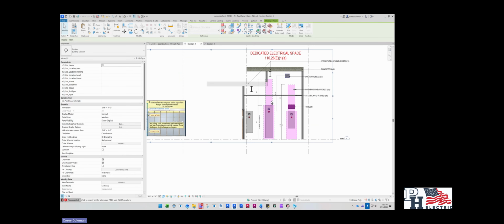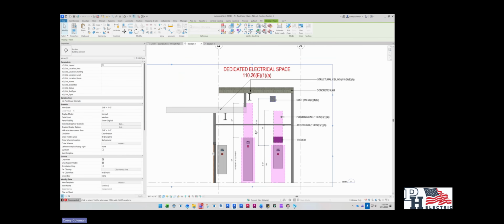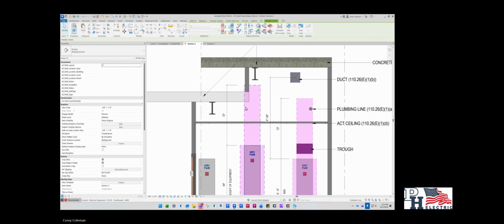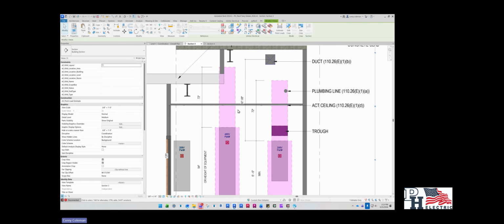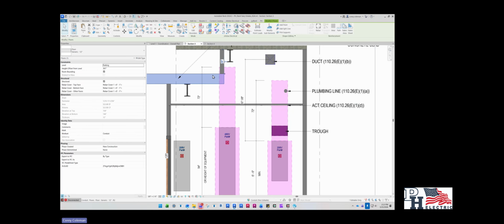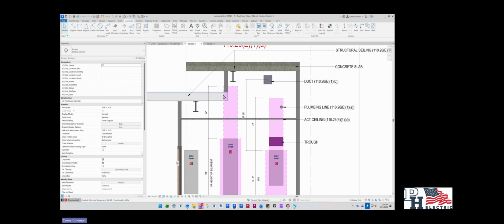And then lastly, when we're dealing with dedicated electrical space, you can have structural ceilings above it, but you cannot have any other foreign elements in that space. So for instance, this ACT ceiling, because of 110.26(E)(1)(d), is allowed to be here as a removable ACT ceiling. It does not count as a structural ceiling, however. However, this slab up above does.